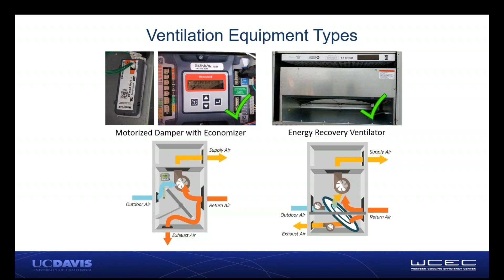And then the last piece of equipment I show here is kind of interesting. This is a Bard ventilator option for their equipment. It has an enthalpy wheel, and the heat is recovered from the exhaust air and used to either pre-cool or preheat the outdoor air going into the classroom. In a current phase of study that we're doing, it was an intervention study where we actually affected the type of equipment that is installed, and we're monitoring it very carefully. So we're doing a very detailed analysis of the energy performance of both energy recovery ventilators and economizers, specifically for classroom portables. Next slide.